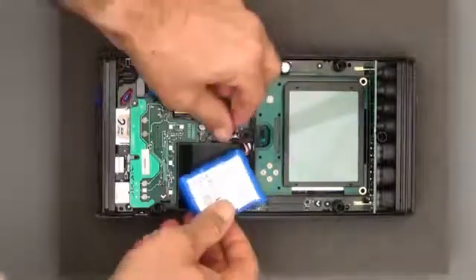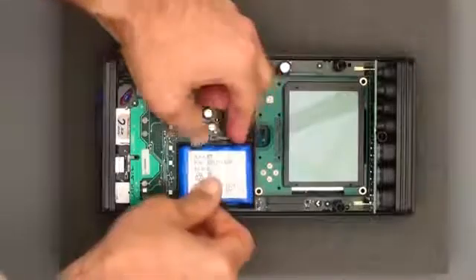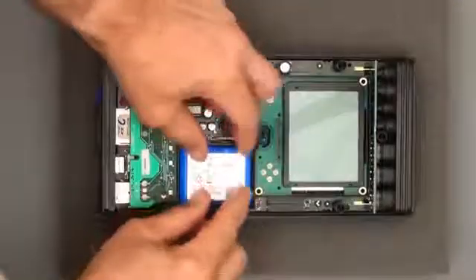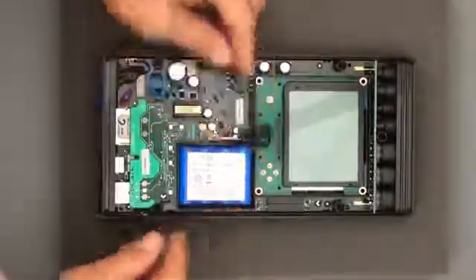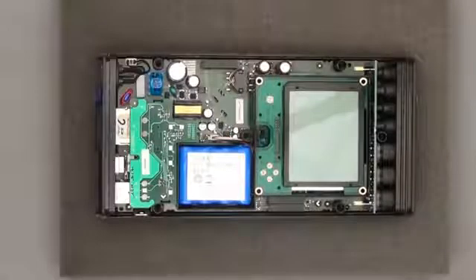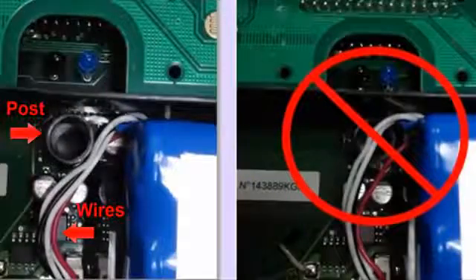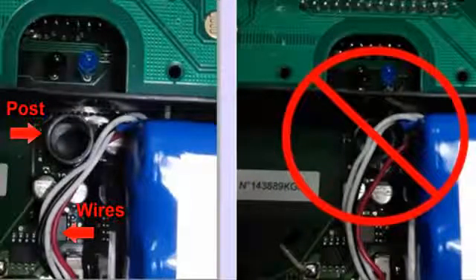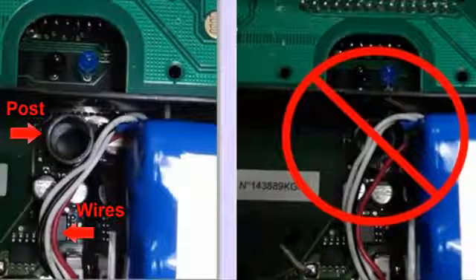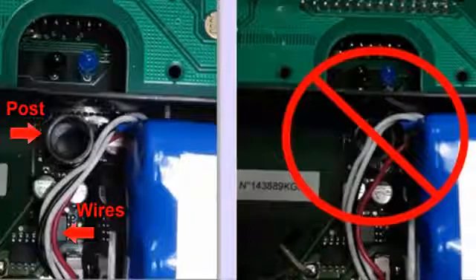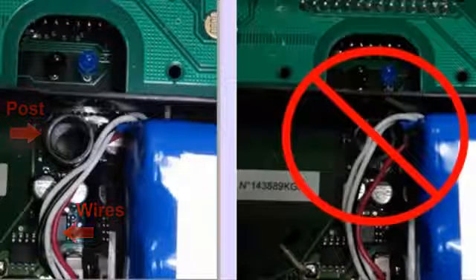The PEL instrument will likely turn on when you plug in the connector. This can be disregarded. Place the replacement battery into the compartment provided for it within the PEL. When doing this, ensure that the battery's connector wires are positioned as shown in the illustration on the left. Be sure the wires do not cross over the top of the post, as shown on the right. If the wires are placed over the post, they will likely be damaged when you replace the front cover.